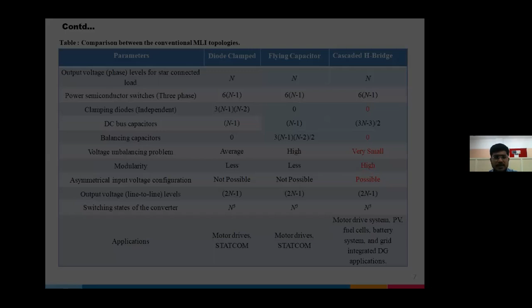If you see the comparison of these three topologies together, more or less all three need switches. The diode clamped one requires diodes, whereas flying capacitors require additional balancing capacitors. Whereas in the cascaded H-bridge, you don't require any diodes or any capacitors. In these two topologies, since you are providing one DC source, you have to maintain the capacitor voltage, so balancing issues arise. Whenever you design a topology for an application, not only from the load point of view, you have to take care of capacitor voltages, so your control strategy complexity will increase.